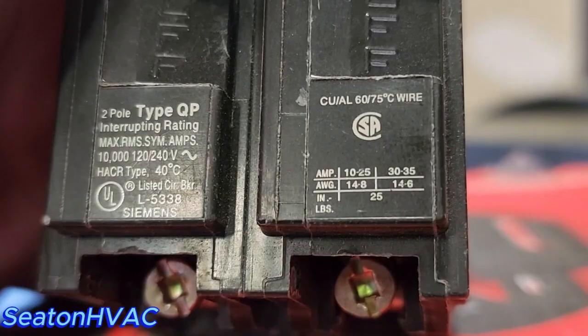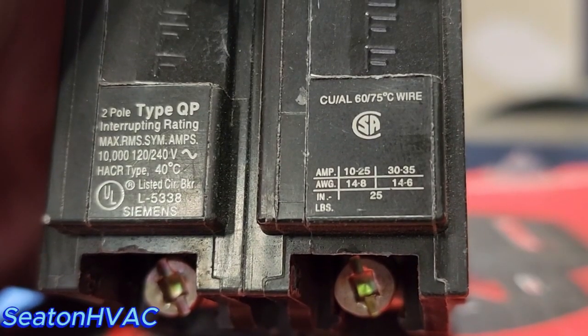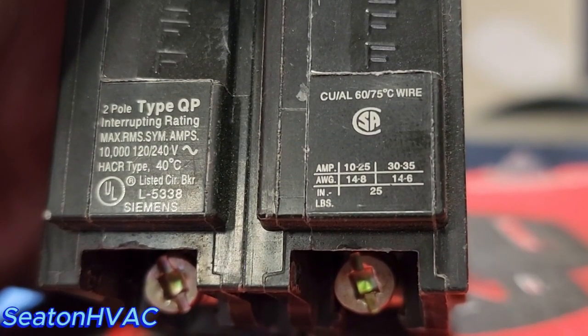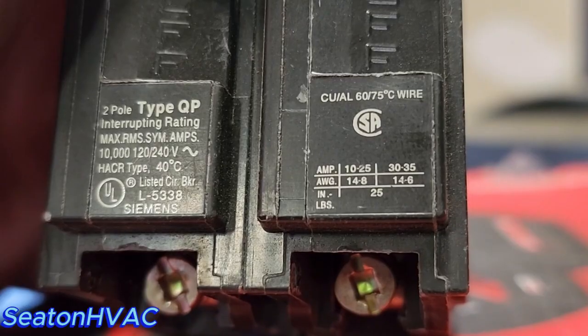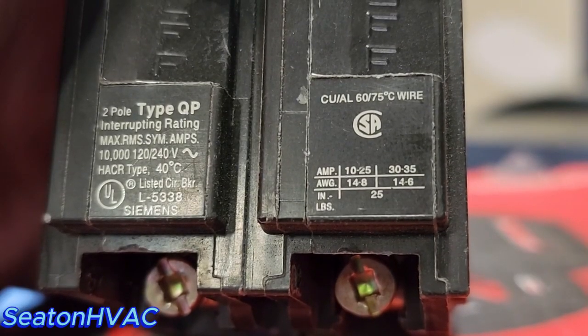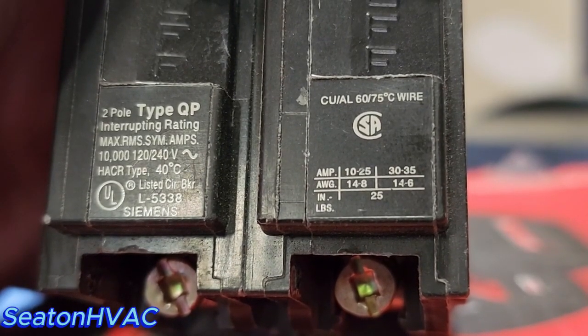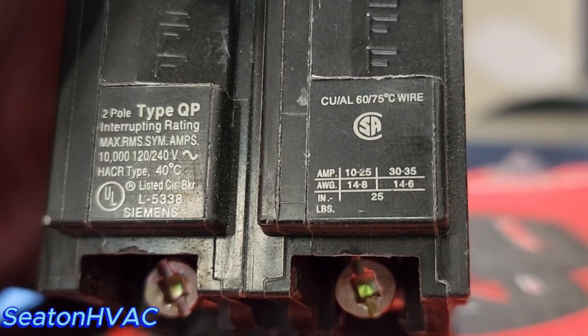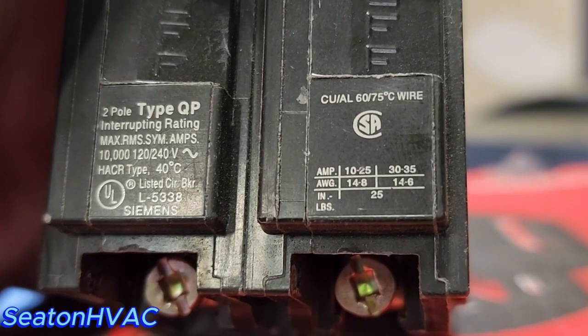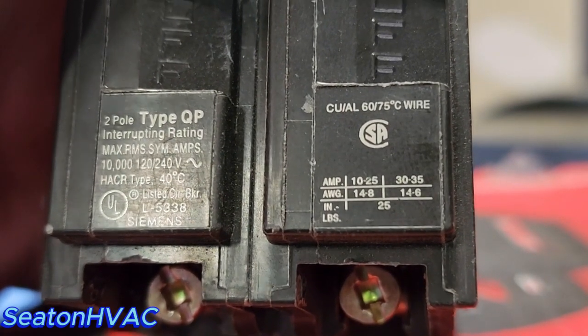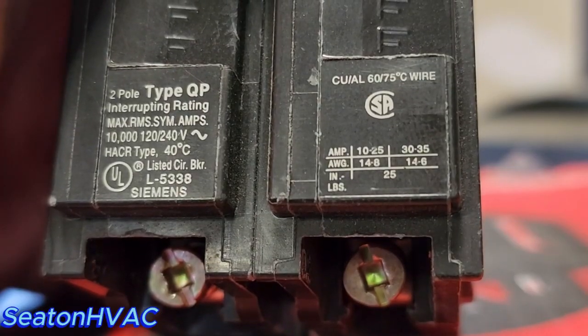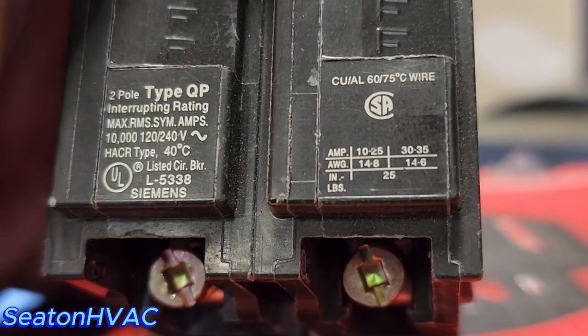But it's telling you what gauge of wire you can put in there: 14 to 8, 14 to 6. I'm assuming it's telling you that's your minimum and that's your maximum on your amperage, and then that's your minimum and maximum on your gauge of wire. Then it gives you the inch-pounds you want to torque them down to: 25 inch-pounds of torque on your wires.